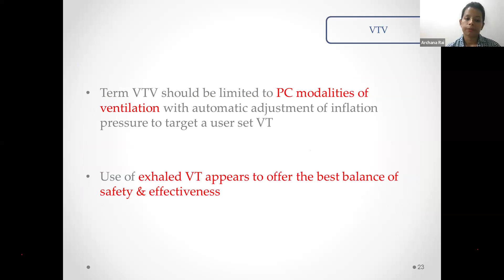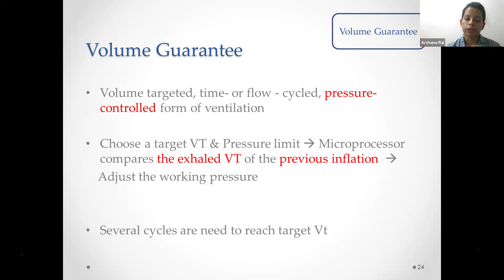In this, we first choose the VT target, what we have set as per the baby's condition, and a pressure limit. Then the microprocessor will compare the exhaled VT of the previous inflation, and then it will adjust the working pressure. At this time, we have to keep looking at the working pressure, because the pressure limit we have set has to be reset depending on the working pressure as per the baby's clinical condition. It should usually be set 3 to 5 centimeters above the working pressure. And usually several cycles of inflations are needed to reach a target VT.